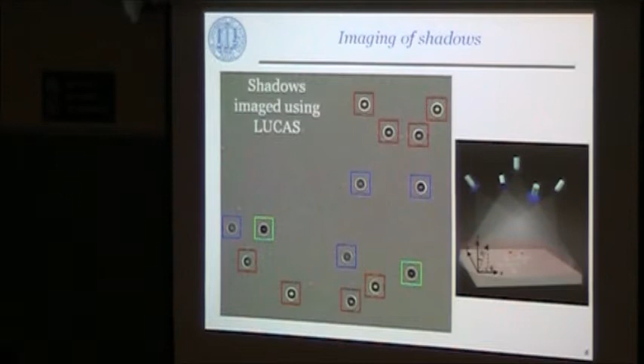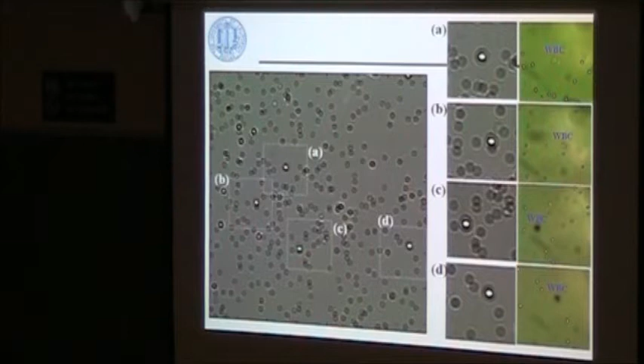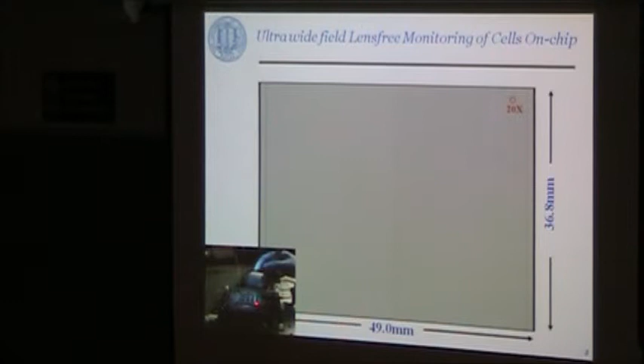If you look at whole blood, you'll be seeing mostly red blood cells. These are actually the shadows of red blood cells. Every now and then you would see another one, which is coming from the white blood cells. This simple shadow imaging platform can do cytometry based on this fingerprint analysis over very large areas. If you're looking at a benchtop system like this, which is a CCD with an active area of around 18 centimeters square, then you'll be looking at these holographic shadows over 5 centimeters by roughly 3.7 centimeters. And you would be seeing these diffraction patterns, which can enable you to count cells.